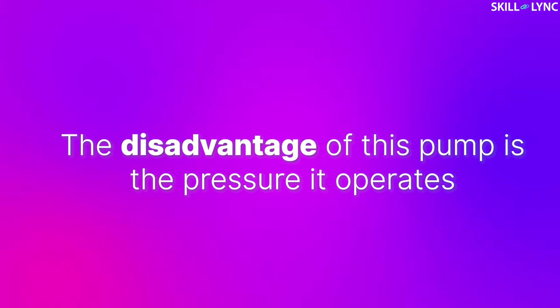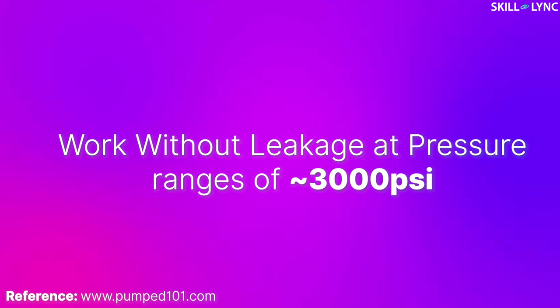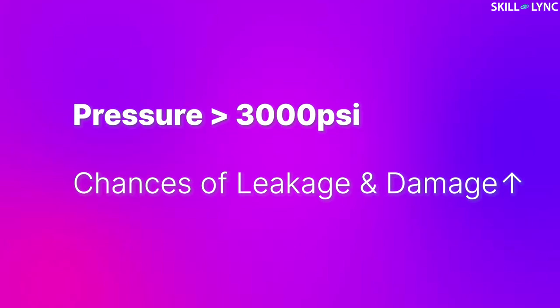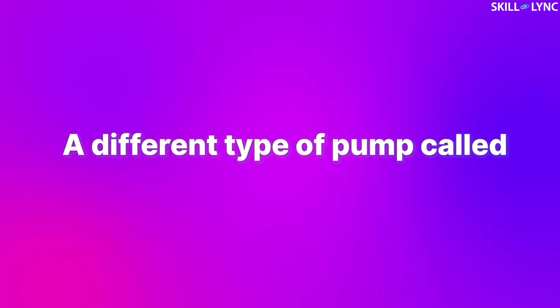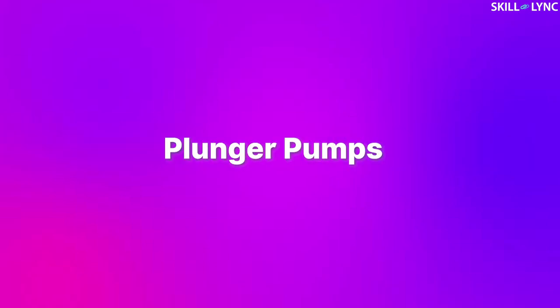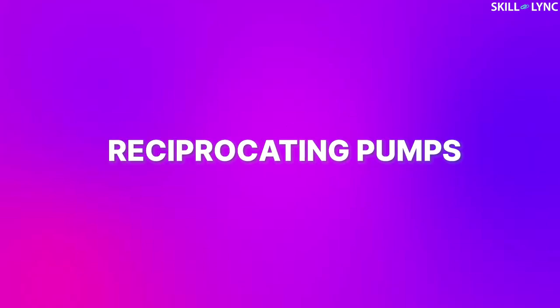The disadvantage of this pump is the pressure it operates at. Piston reciprocating pumps can operate effectively without leakage at a pressure range of up to 3000 psi. Any higher, the chances of leakage and damage to the piston are high. To avoid this, a different type of pump called a plunger pump is used. We'll be talking about more reciprocating pumps in our next video.